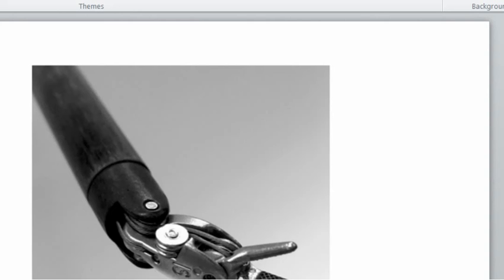A similar control architecture was also implemented on the master hand controller side. During operations, the position of the grasper tips is compared with the reference input generated at the master hand controller. If a difference, a position error, is detected, as is usually the case when tissue is being grabbed, a grabbing force is automatically detected and reflected to the master hand controller. Mechanical properties of the grabbed objects, such as tissue hardness, can also be felt.